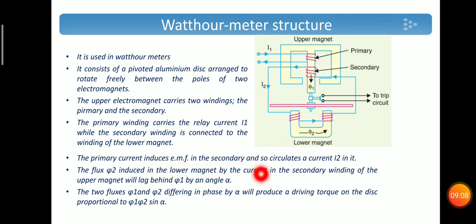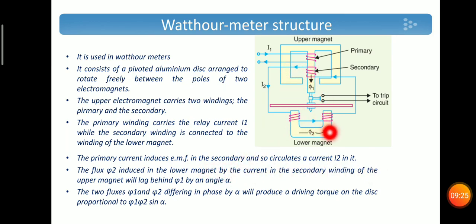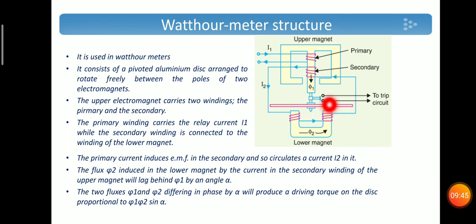The primary current induces an EMF in the secondary and circulates current I2 in it. The flux phi-2 induced in the lower magnet by the current in the secondary winding of the upper magnet will lag phi-1 by an angle alpha, creating a phase difference between the flux produced in the upper magnet and the lower magnet. This gives a driving torque of phi-1 · phi-2 · sin(α), and as the disc rotates to a certain angle, the trip circuit gets closed.